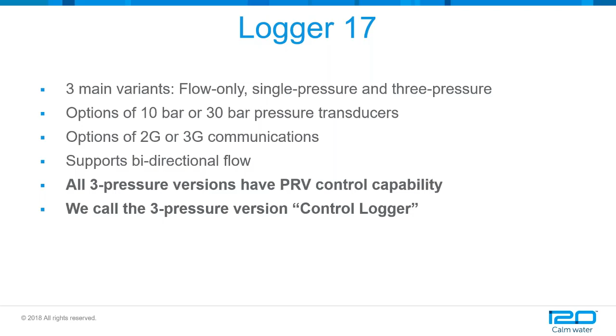So just a little bit about the differences with the new Logger 17 and control logger. Those of you who are familiar with Logger 14 will be used to the metal connectors that we have. On the Logger 17 we have plastic connectors, and you can see they're color coded.